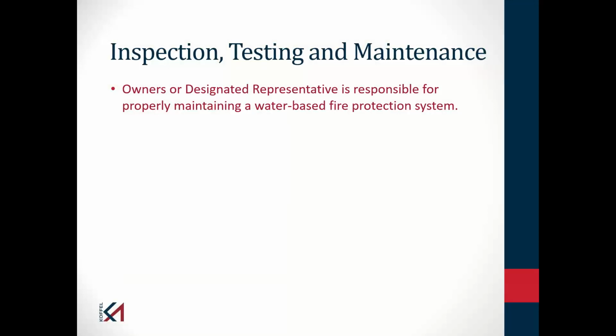Overall, the owner or their designated representative is responsible for proper maintenance of any water-based fire protection systems. That is explicitly stated in NFPA 25. It's explicitly stated in fire codes. Attorneys love that statement. When I do a construction defect case, it's not always clear who's responsible for the non-compliant condition. Was it the contractor, the design professional, a subcontractor? And all that gets settled through the litigation.